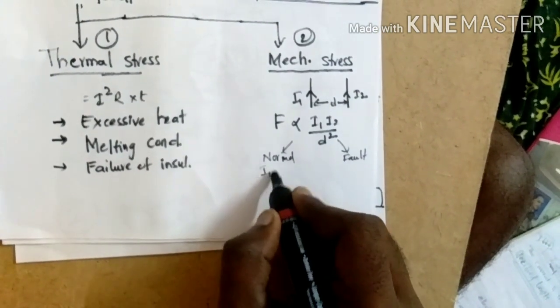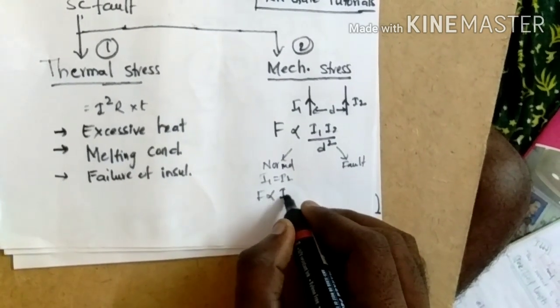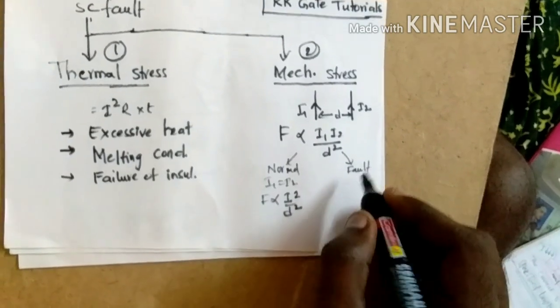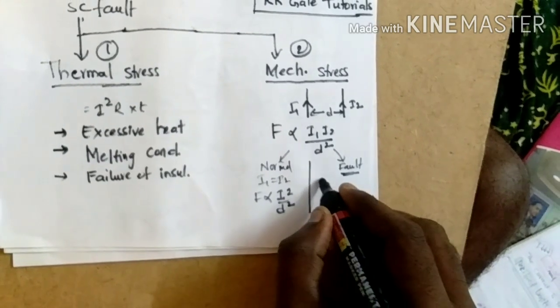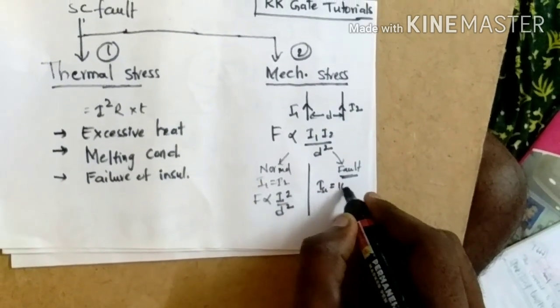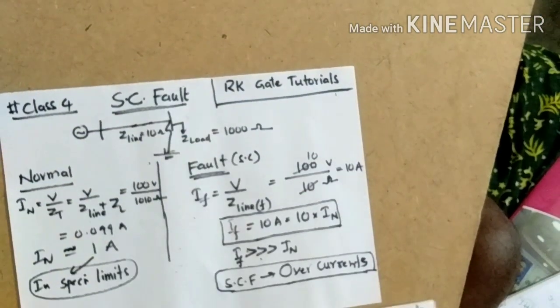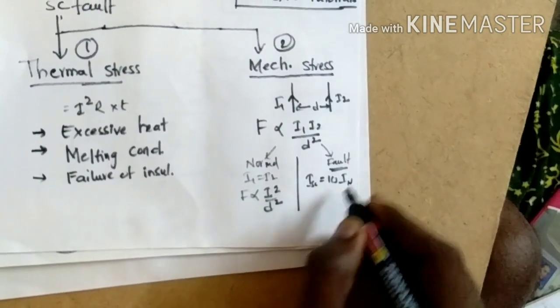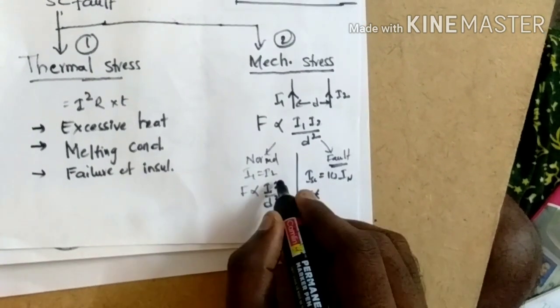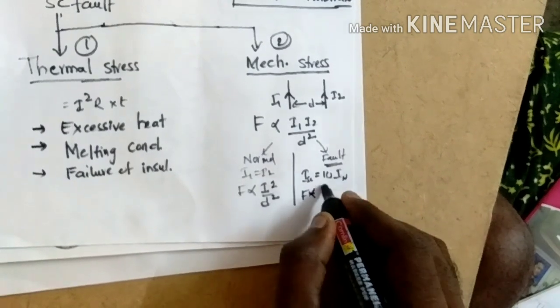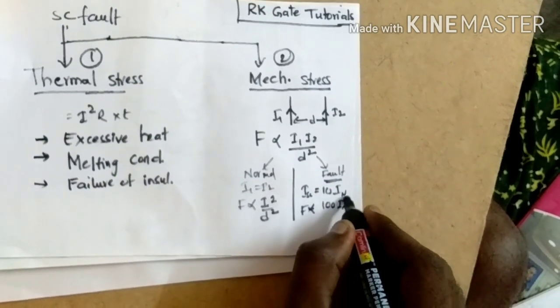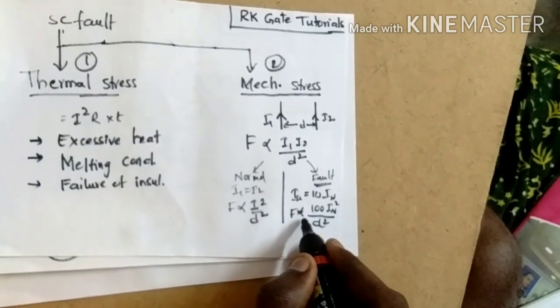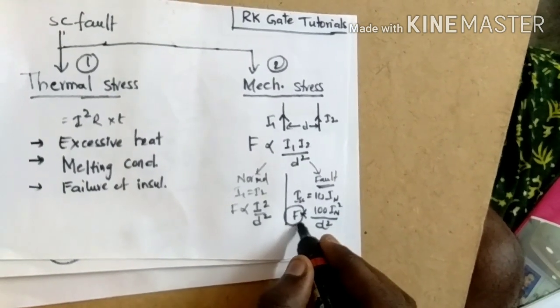During normal condition, the force is proportional to I² divided by d². During short circuit fault condition, the short circuit current is 10 times the normal current, as we calculated earlier. So the force becomes proportional to (10·I_n)² divided by d², which equals 100·I_n² divided by d². The force increases enormously — 100 times the normal force.